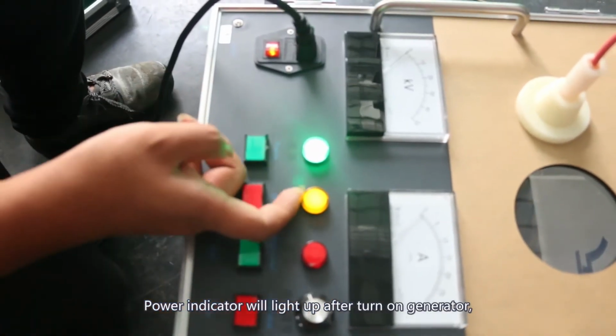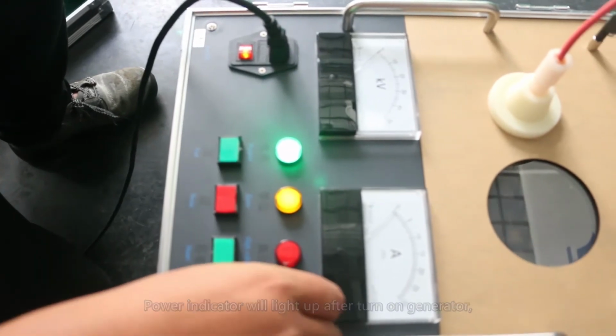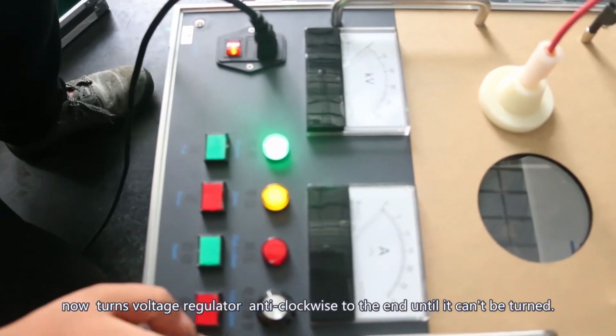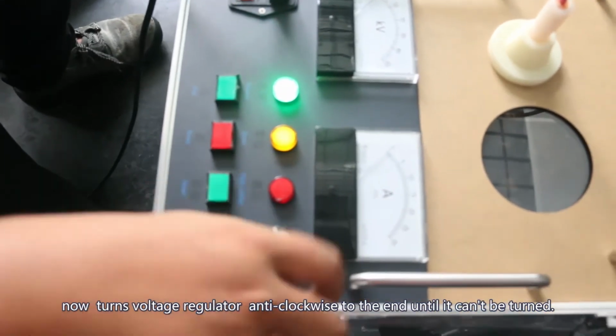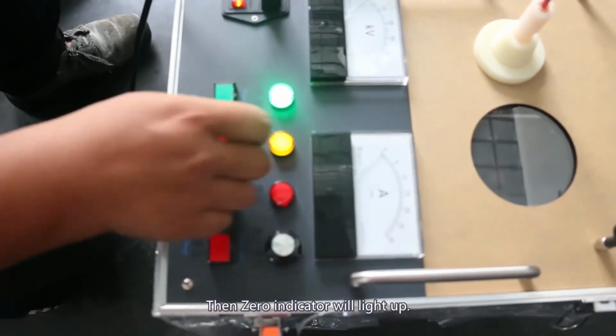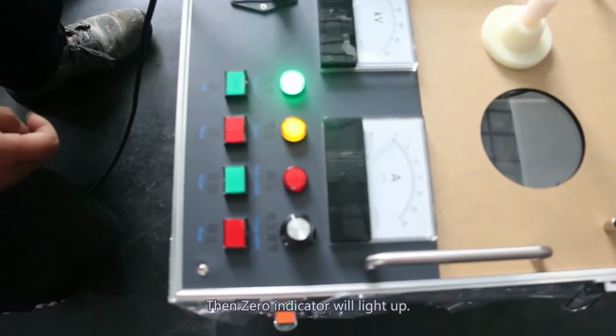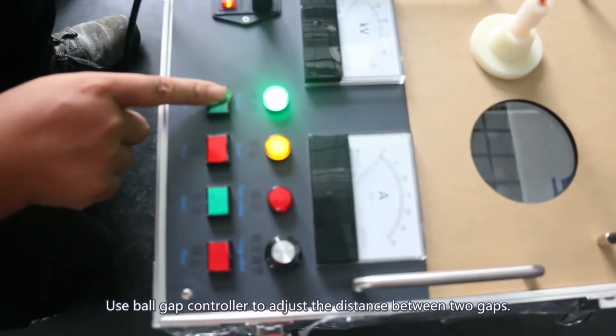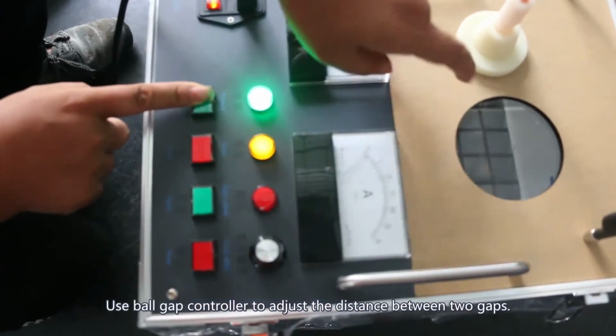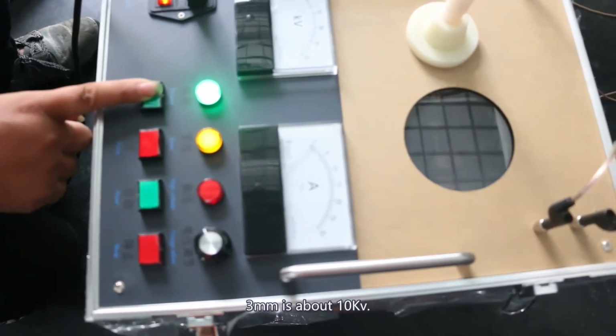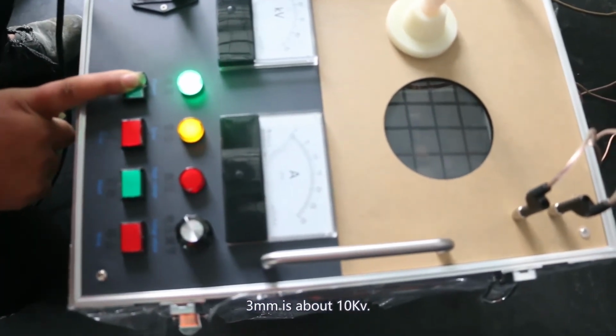Power indicator will light up after turn on generator. Now turn voltage regulator anti-clockwise to the end until it can't be turned. Then 0 indicator will light up. Use ball gap controller to adjust the distance between 2 gaps. 3 mm is about 10 kilovolts.